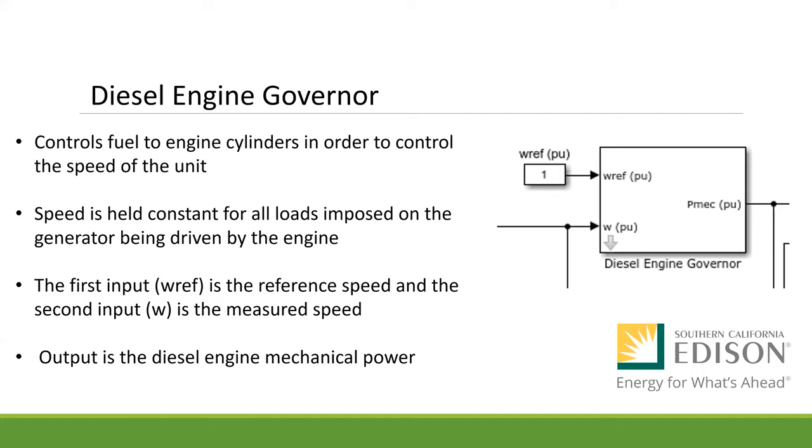The diesel engine governor controls fuel to engine cylinders in order to control the speed of the unit. The speed is to be held constant for all loads imposed on the generator being driven by the engine. The first input is labeled WREF and is the reference speed. The second input is labeled W and is the measured speed. Output is the diesel engine mechanical power.